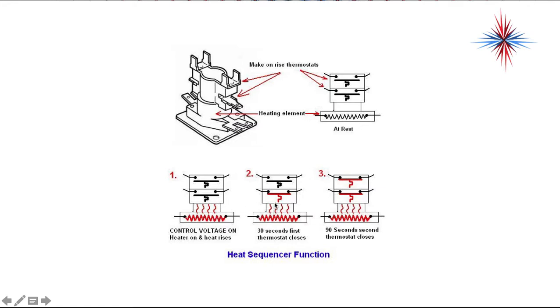After 30 seconds, the thermostat closes and that first stage will come on. That first stage is normally your blower motor and your first stage of electric heat. This will continue to give off heat, and then 90 seconds later, or whatever it's timed for, the second stage of heat would come on, and this would just continue that way throughout however many stages.